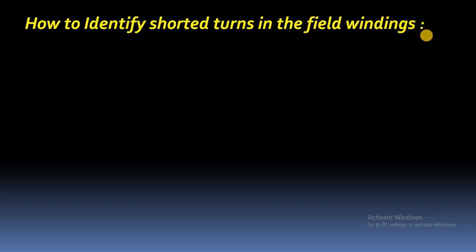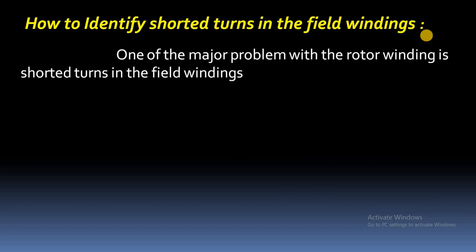These shorted turns are one of the major problems with the rotor winding. They exist because of insulation failure of the rotor winding, the aging of the rotor winding, and because of the thermal stresses of the rotor winding. These are the major reasons for shorted turns in the field winding.